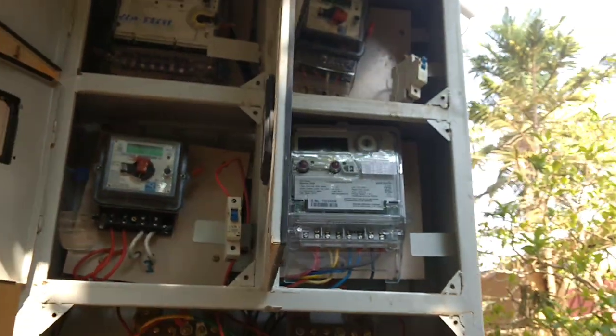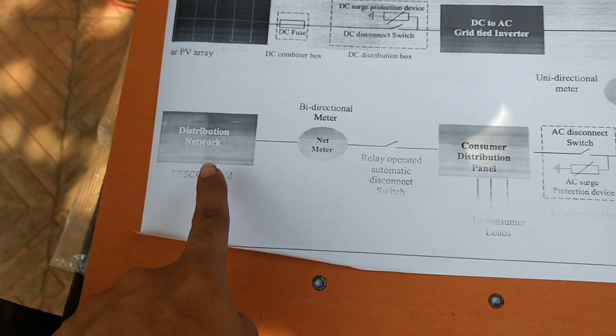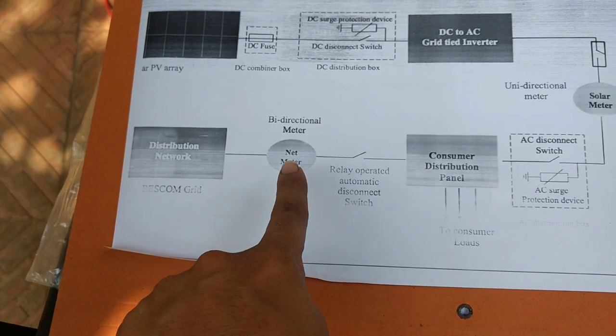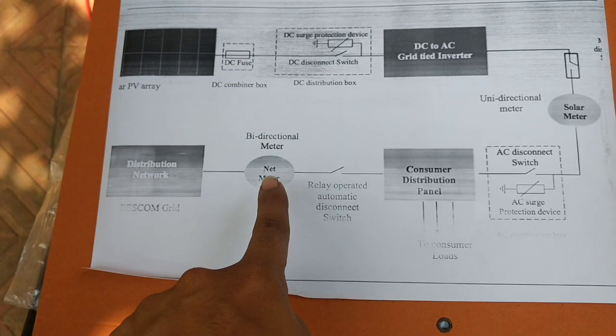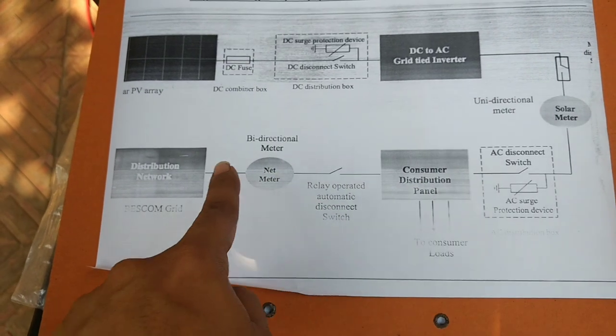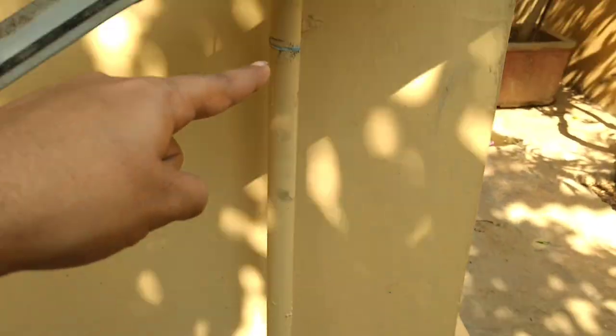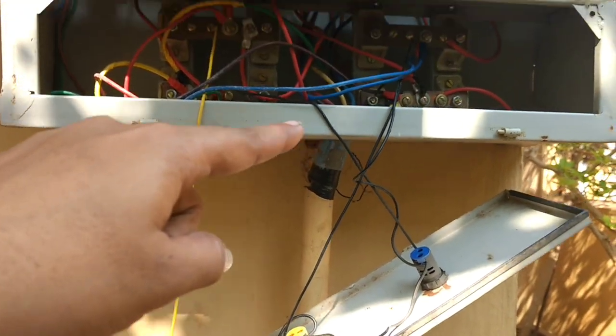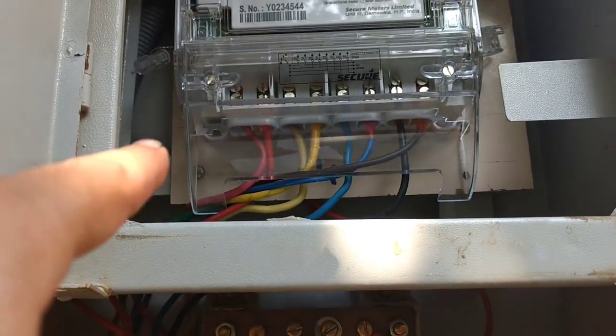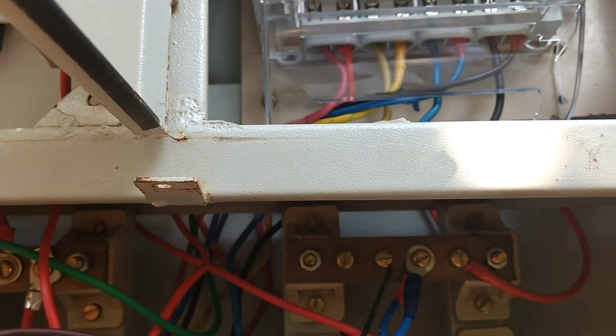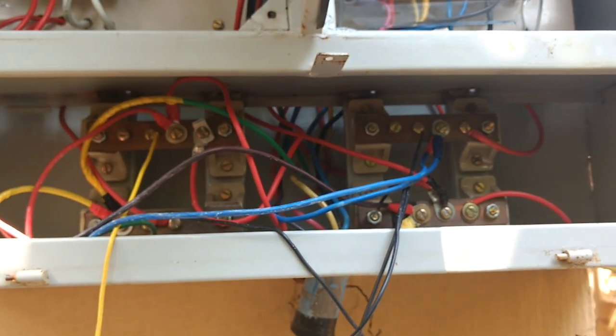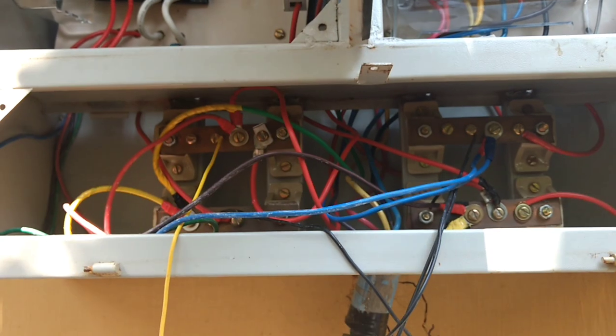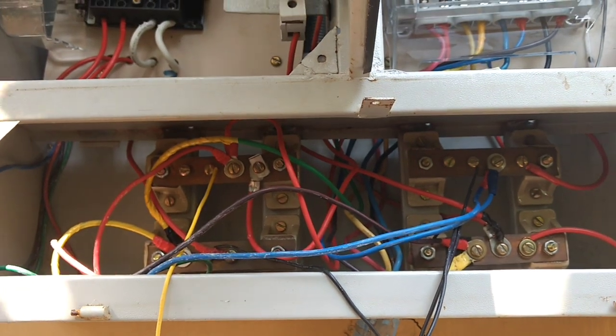I have a drawing with me. See, from here the grid is coming to the bi-directional meter and it's going towards the bus bar. So the output of the bi-directional meter goes to the bus bar. So this is the grid wire. It's going inside the bi-directional meter input ports: R, Y, B, and the neutral. And the output of the meter goes towards the bus bar. And at the same time, this bus bar is connected with the load, that is the house.